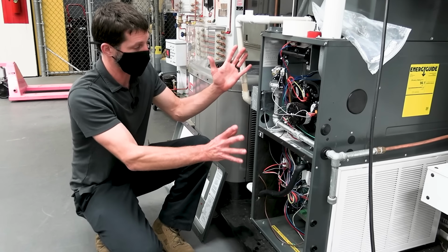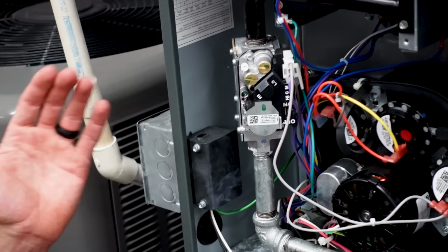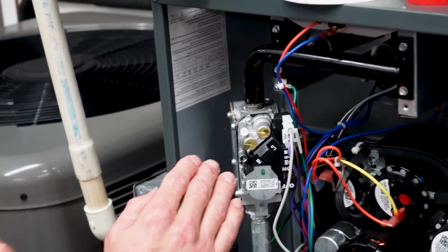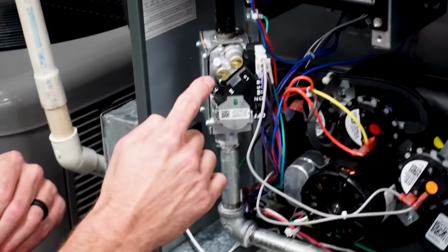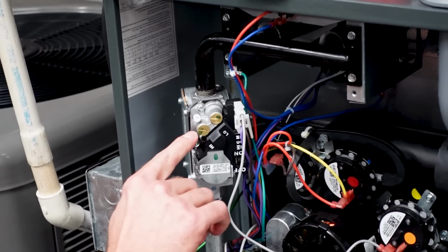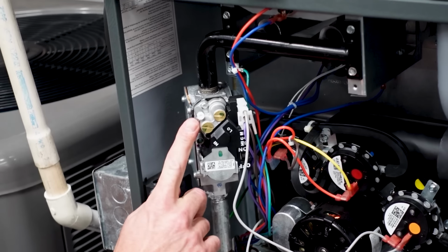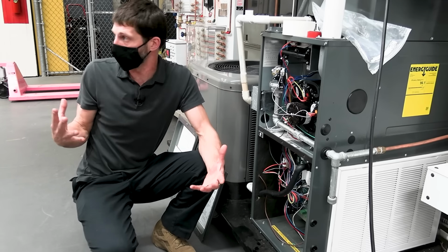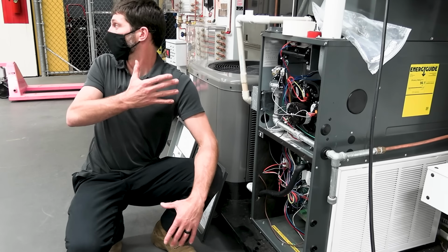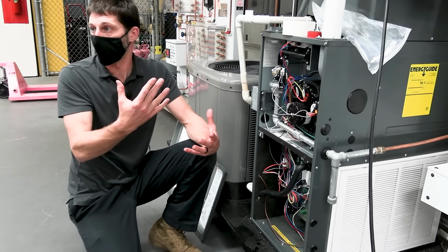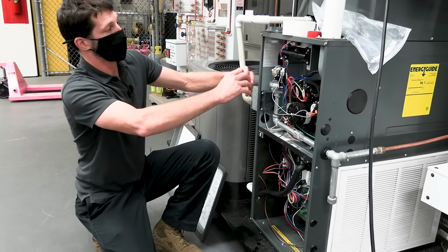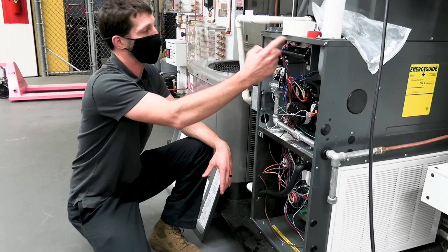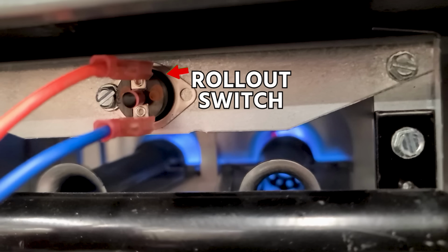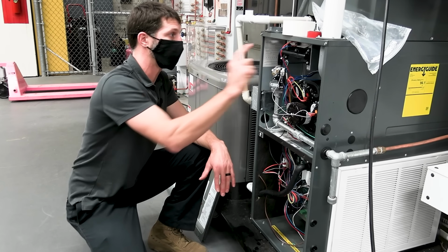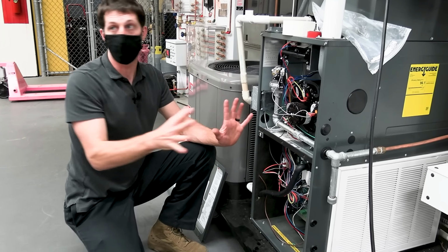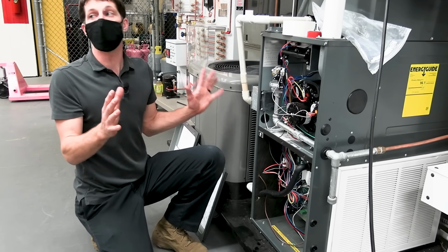If you're setting this as a natural gas system, fine, but if you're doing propane, you absolutely need to adjust these, and you'll have a problem where the furnace isn't going to turn on unless you first initially tighten that plastic insert in the correct amount of turns inwards, just in order to get it close enough for it to fire correctly. Otherwise, you're not going to have enough gas pressure to ignite it properly, or it's going to ignite in a way where it could potentially pop this flame rollout switch right here. And just so you know, you should never be continuing to reset a flame rollout switch. There's a problem. And it doesn't necessarily mean it is a cracked heat exchanger right away.